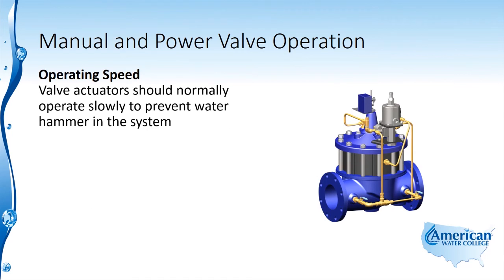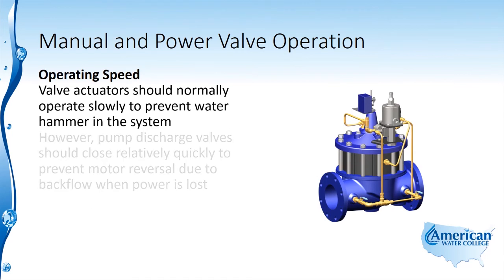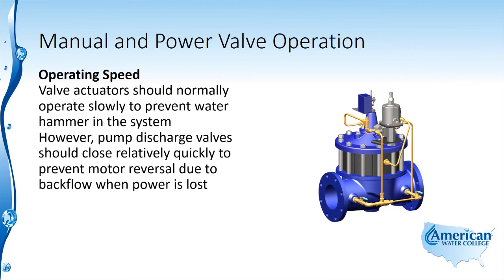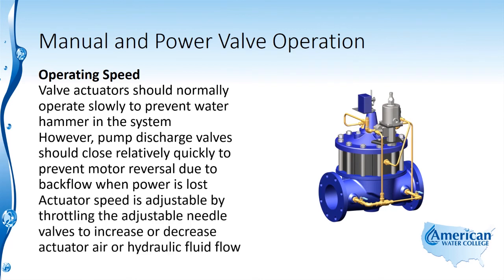Valve actuators should normally operate slowly to prevent water hammer in the system. However, pump discharge valves should close relatively quickly to prevent motor reversal due to backflow when power is lost. Actuator speed is adjustable by throttling the adjustable needle valves to increase or decrease actuator air or hydraulic fluid flow.